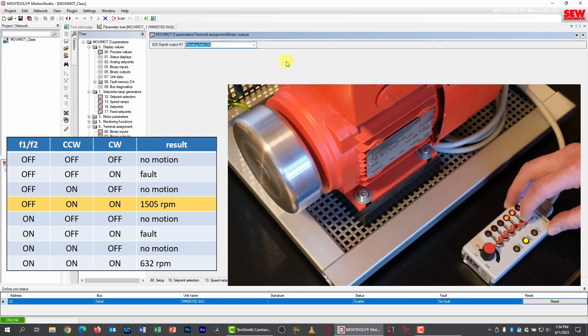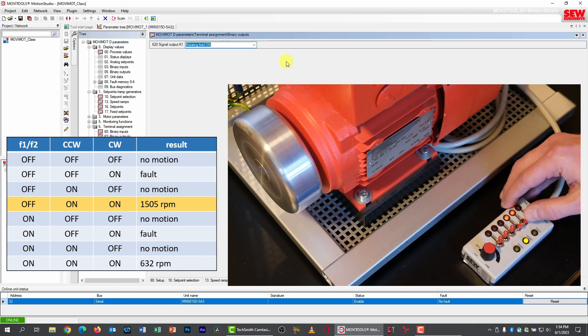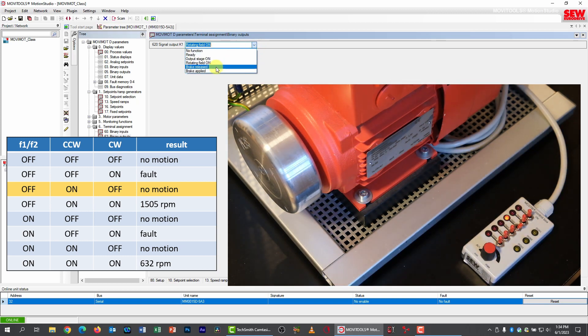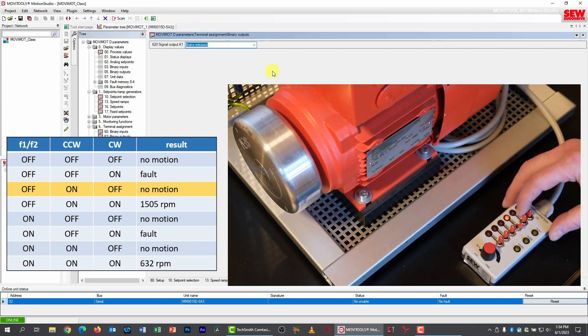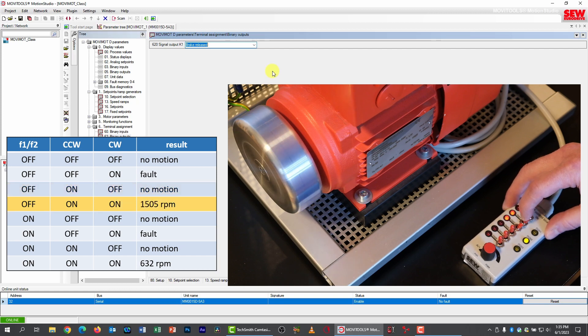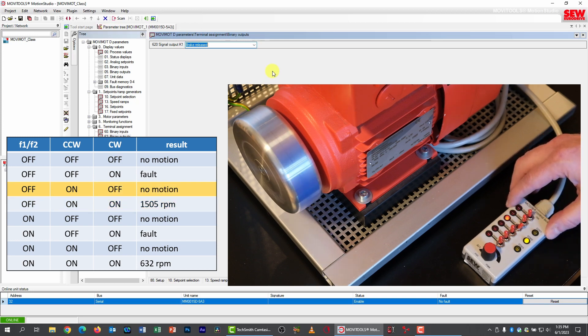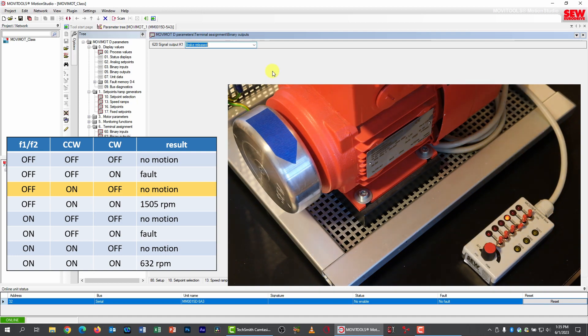I'll also show what an immediate stop looks like. I change the fault response to immediate stop. My demo unit has a brake, so as soon as the fault triggers, it shuts off the output transistors and slams on the brakes — giving a very quick stop. However, if there were no brake, the drive could coast a long time with a big load. So immediate stop is usually not advisable without a brake, but with a brake you'll get a quick stop. I also demonstrate changing the digital output relay assignment to rotating field on, then brake released, showing different status signals controlling the relay contact.